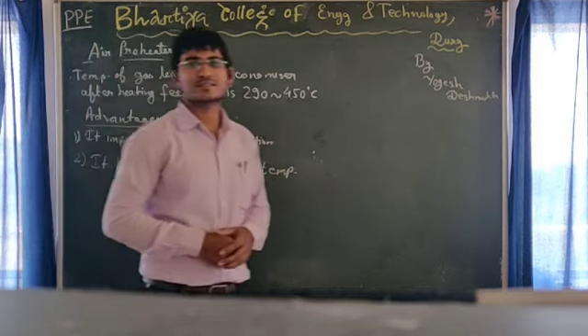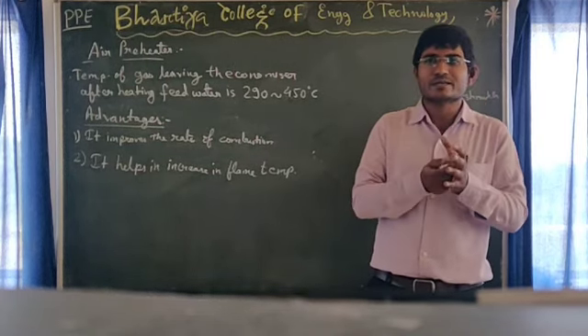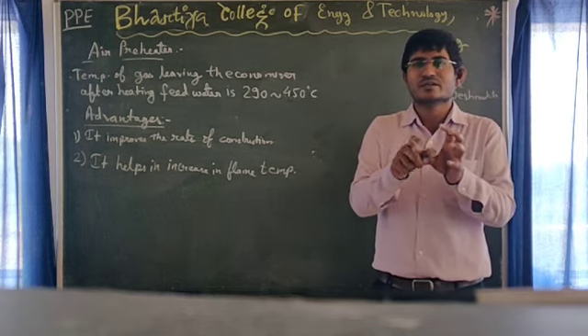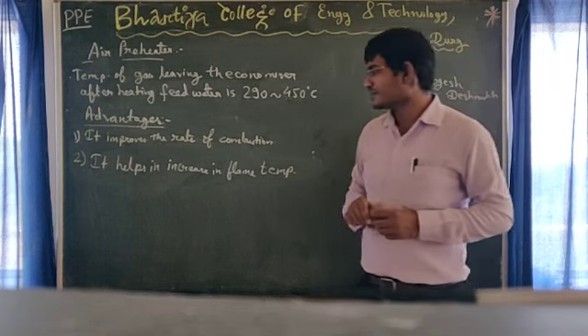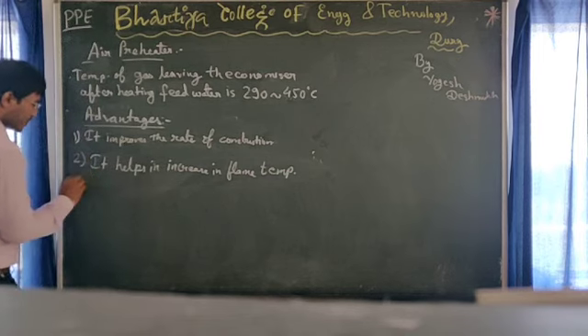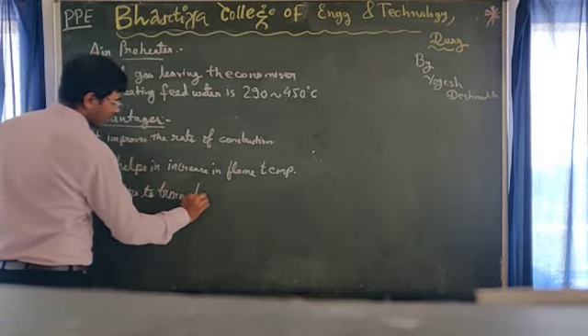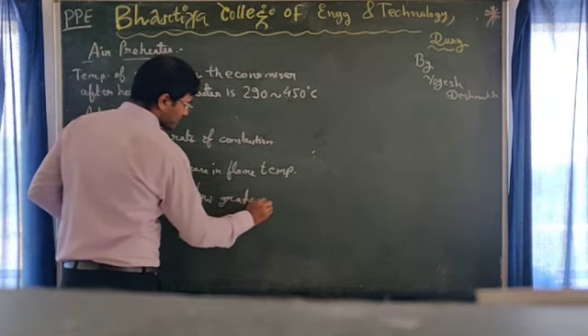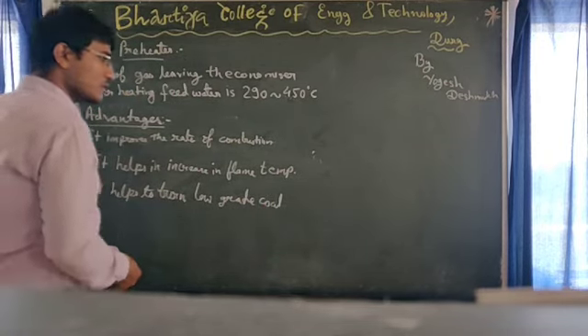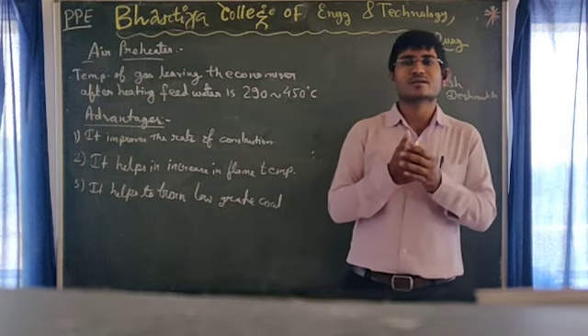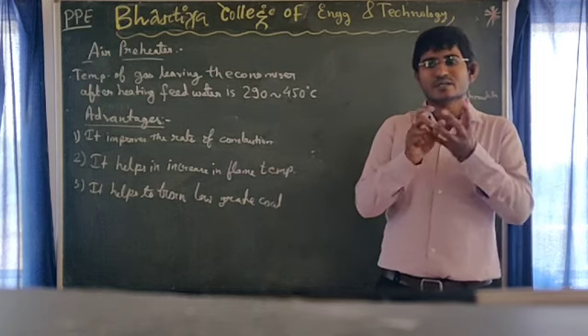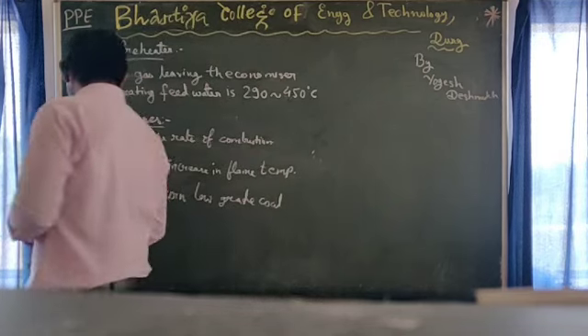The temperature of the flame increases because as combustion is going on and hot air flows in, the air contains oxygen and it improves the combustion conditions. With hot air it also improves the temperature, thereby increasing the flame temperature. Third, it helps to burn low-grade coal. As we are supplying hot air, even low-grade coal will get heated easily and will burn properly. Hence, it helps in the burning of low-grade coal.